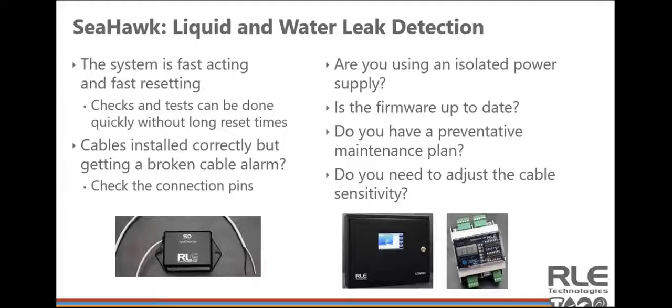We also have a product called a weighted cable connector, which is great for adding a simulated 50 feet between cables or points. So if you're trying to set up a room and map it, and the cable feeds from one room right into another, throw a weighted cable connector in there. That'll add that 50 feet of separation, so it's a clear sign when you get a footage reading of which room your leak is in.